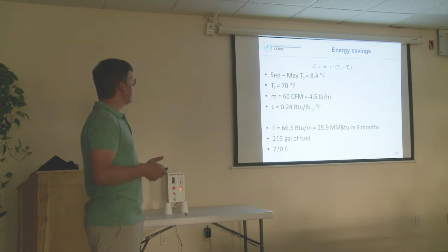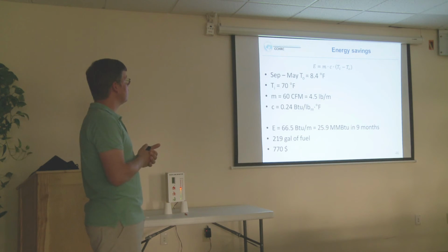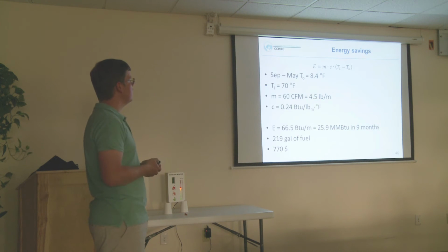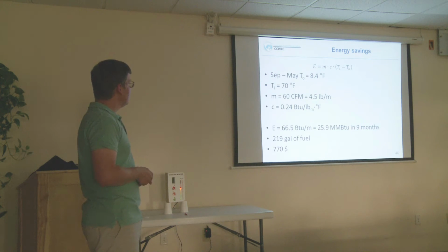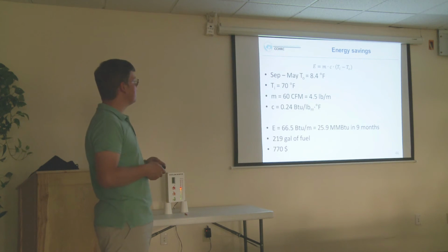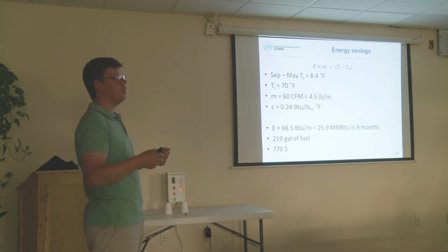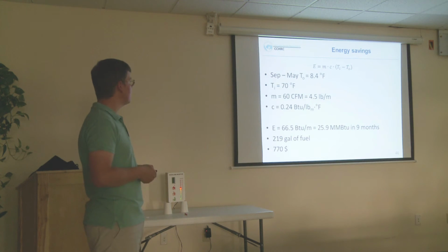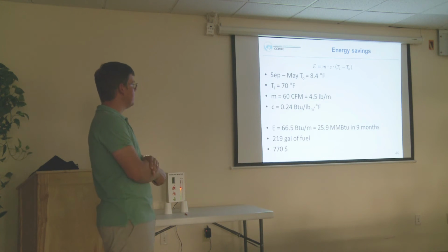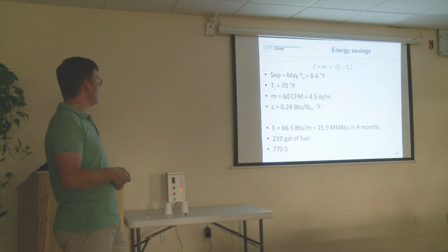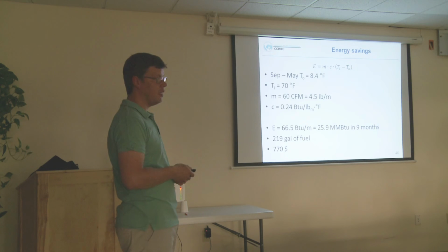So why is it saving energy? Well, because of the heat recovery, and there is a little example again on the Fairbanks situation. I took 9 months from September to May with the average temperature of 8.4 degrees Fahrenheit, indoor temperature 70 degrees, and I took that house we had on the very first example, so we'll have 60 cubic feet per minute of ventilation air. The heat capacity of the air we have here. So if we for some reason decide to ventilate that home without a ventilation unit, just opening the windows as much as is needed to maintain 60 cubic feet per minute ventilation, we would need about 26 million BTUs in those 9 months. That converted into oil and money is about $770 for that 9-month period, if all that air should come in through windows and be heated with our heating system.